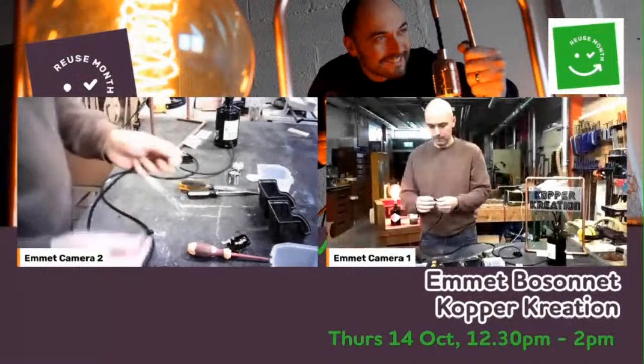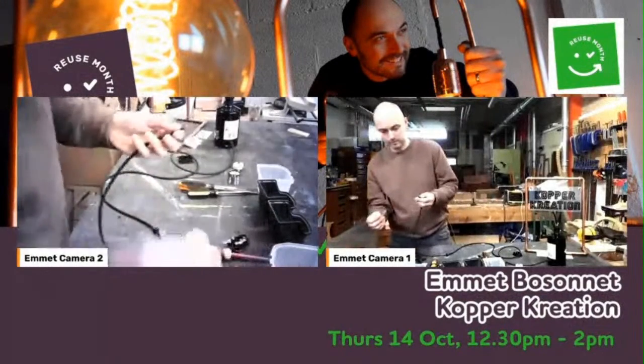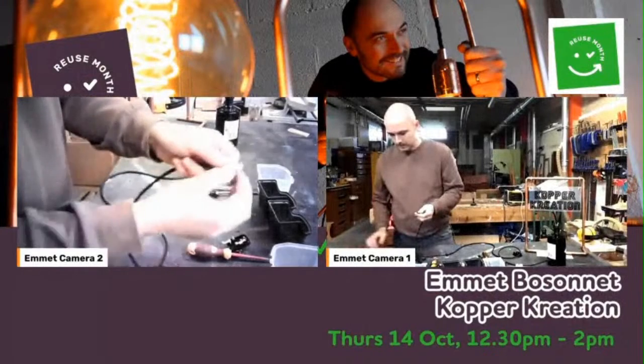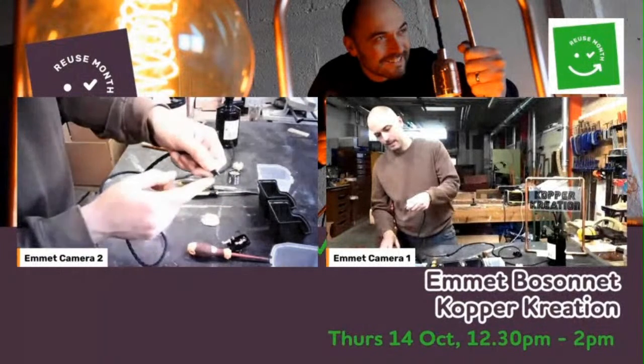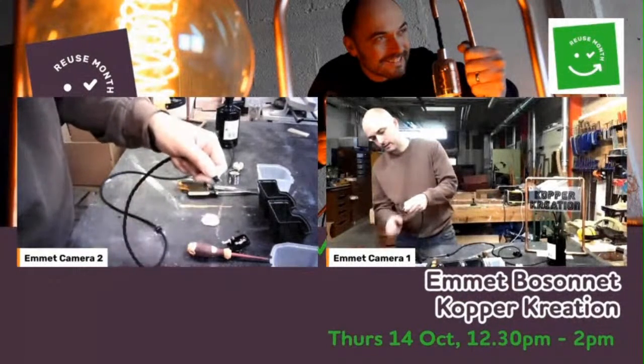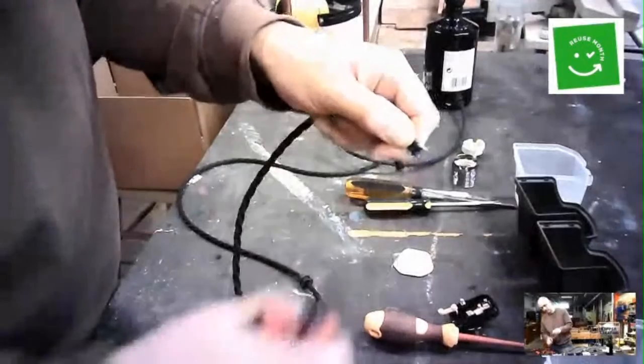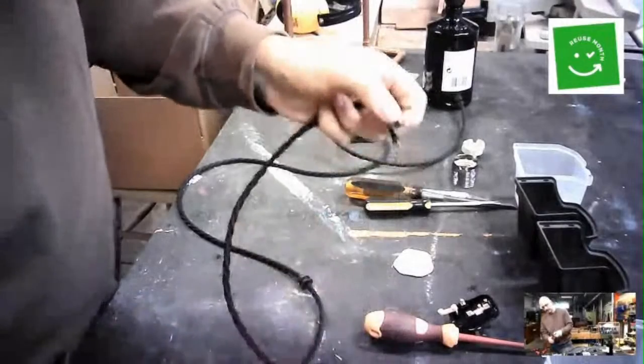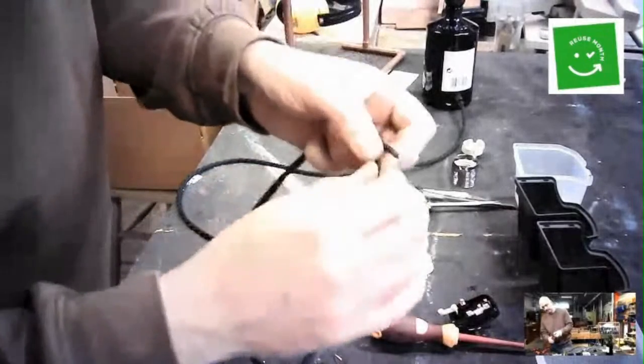So now you can measure these out with your little card exactly. I'm kind of used to doing it by hand. So what I typically do, if you want another tip, is line up your neutral cable next, your blue with your earth, and trim it right where the end of the ferrule meets the yellow and green. Near enough, doesn't have to be bang on. And then you want to pop a trim on that, and then another little rubber guy. Again, you want to terminate it.